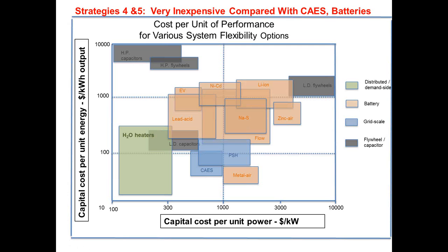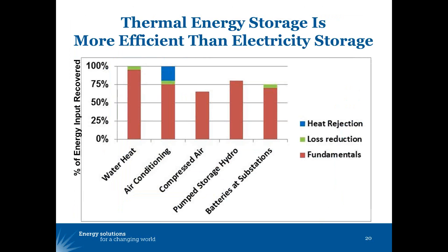If I add water heaters to this, it is at the low end of both the energy and capacity range. A water heater sells for $500, and it can hold 15 to 25 kilowatt hours. It is dramatically cheaper than any other form of energy storage. Chilled water and ice thermal storage also fall at the low end of both the capital cost per kilowatt hour and capital cost per kilowatt of capacity. So I've spent a lot of time on thermal storage, and the reason is I think it's the least understood opportunity that's out here.